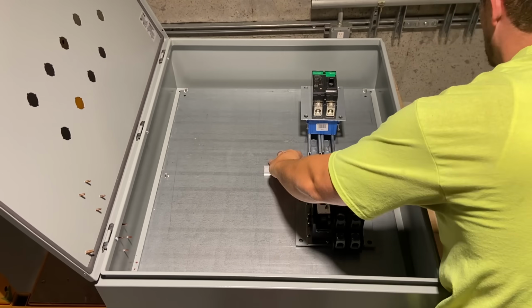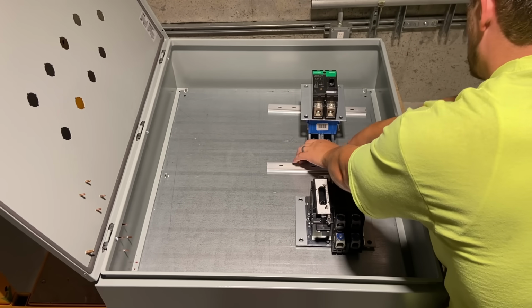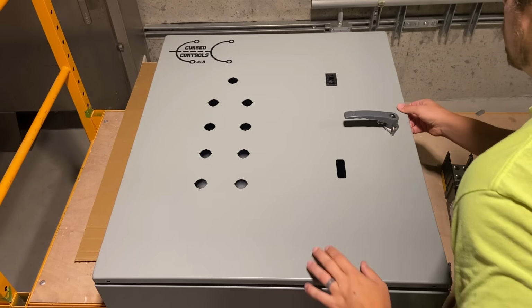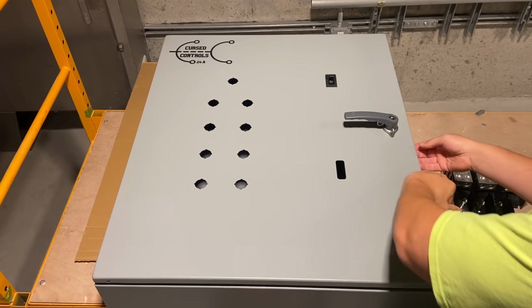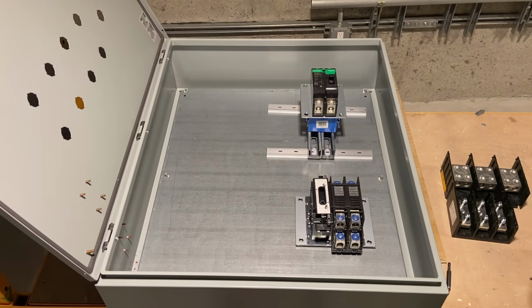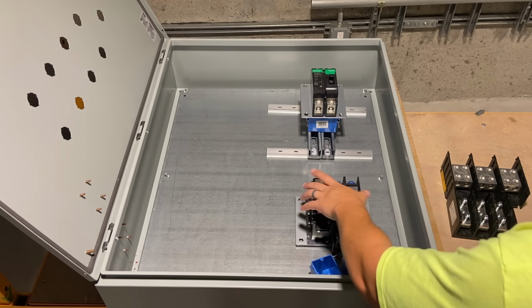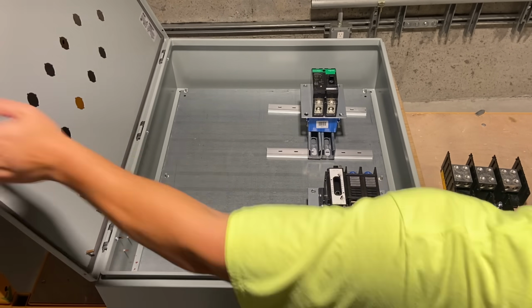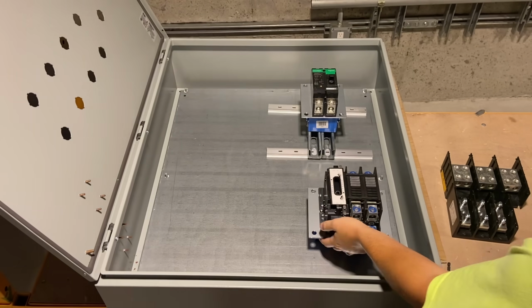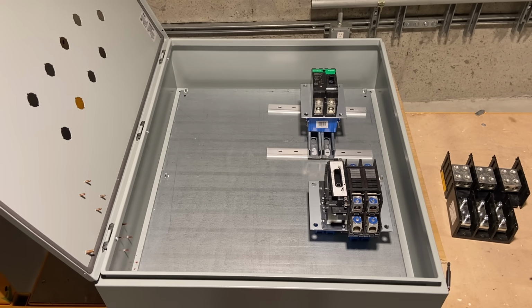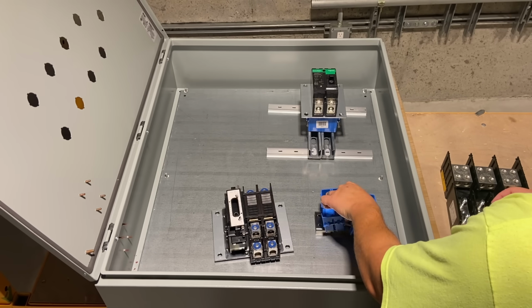It didn't really matter with the push buttons and lights, but with these two devices, they're not going to look quite lined up in the panel, but that's because the holes on the door do line up and are straight. So it was definitely a bit of a change of mindset, because normally I don't have to worry about that. I don't do a lot of panels where things stick out the front, and I hate those rod-mount disconnects, so I don't usually have to do them.